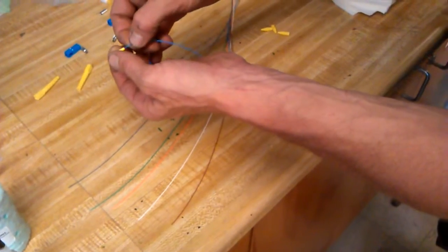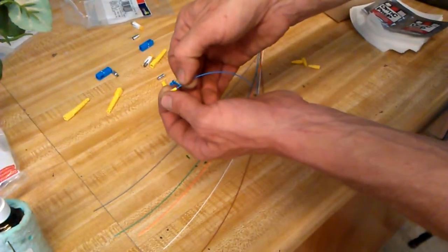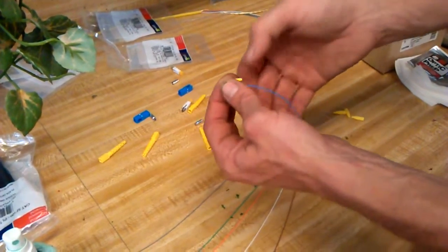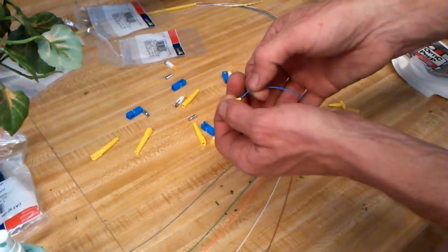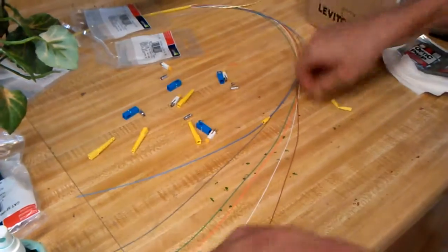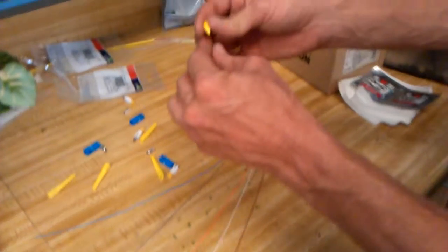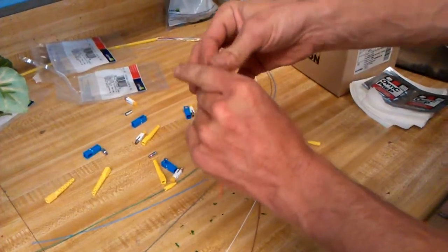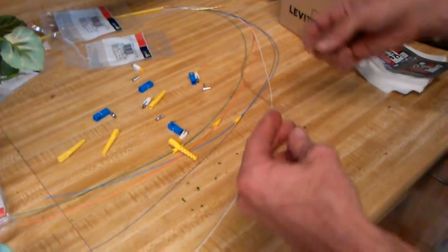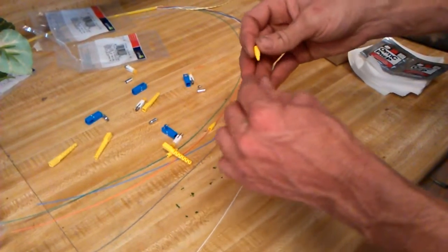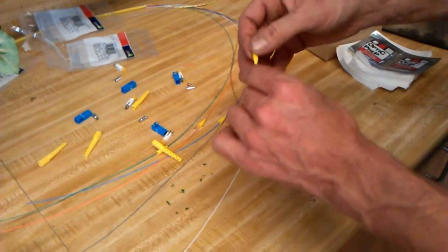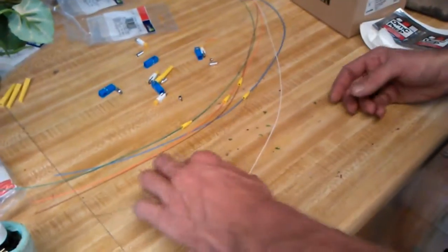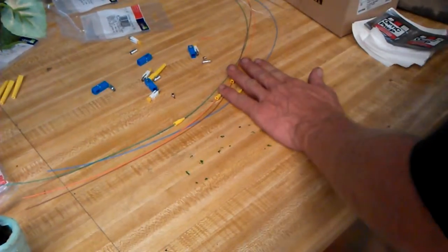The first thing I'm gonna do is put all my boots on before I forget. I've got a blue strand, and notice the closer I hold it the more control I have. I've got blue, orange, green, brown. Now if you forget to put one of these boots on, you could cut it down the middle with a razor and use some super glue. It isn't an acceptable means of doing it, although sometimes in an emergency you have to.